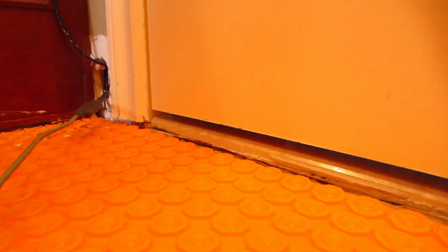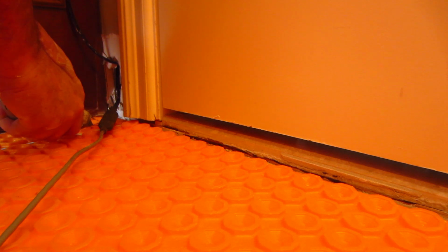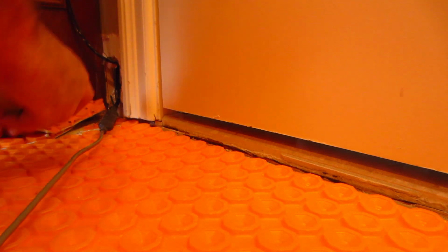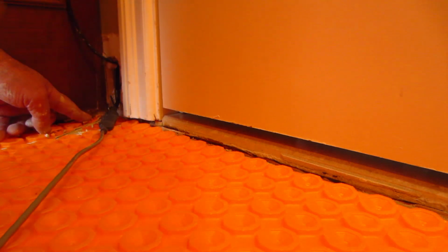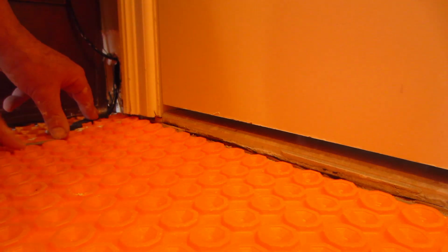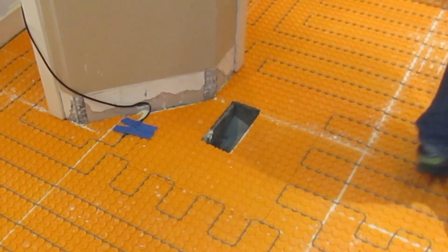I cut this little area out here because this is thicker, so I can go down into the mat and not create a bump. And that'll feed up into the wall cavity. The wire has to stay 3 inches away from a wall. There's no heat vents here because they're in the ceiling. But if there was one on the floor here, you'd stay 8 inches away from it.